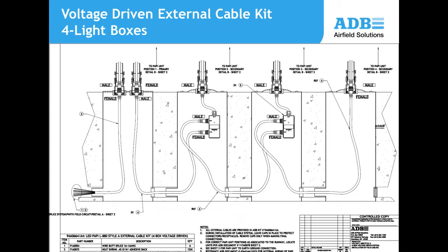To simplify installation, the system uses a set of connector boxes between the various PAPI light units, with pre-connectorized cables connecting to those boxes and then to each PAPI. This eliminates the need to field-splice wiring in each base can to deliver power and signals to each PAPI light unit.